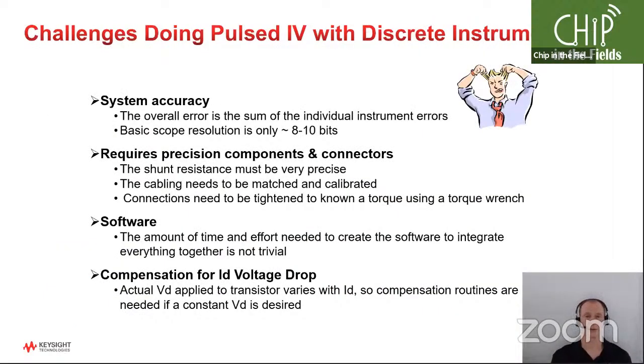So what are some of the problems with the solution I just showed? Well, one of the main ones is accuracy. The errors of the instruments are actually summed together, so you have to add on those different errors, and that's going to affect your accuracy. Scope measurement resolution is not that great. Scopes are really good at time resolution, but not so great at voltage resolution. They typically only have maybe 8 or 10 bits. The precision you need on your components is also very important. You have to have a very accurate, calibrated shunt. Cabling needs to be carefully matched. You need to understand the cable delays in your cabling. And even things like connecting things together properly with a torque wrench to the proper torque, believe it or not, can have a big impact on the accuracy of the measurement.